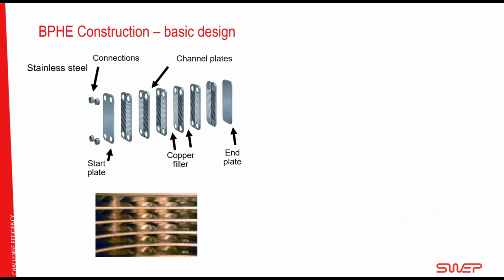Two words about the brazed plate technology. There are other webinars that go more in depth about this. This webinar is about fouling, so I will be very brief here. The brazed plate heat exchanger is made of channel plates, which create the heat transfer area. We have a start plate and an end plate to put everything together and make it strong enough to keep the pressure. All the main components are made of stainless steel: the end plate, the channel plates, the connections, everything. In between the plates, there is a metallic filler, which normally is copper. During the manufacturing process, where we put these heat exchangers in a furnace, the filler material becomes like a metallic glue, keeping the stainless steel plates together. So once they are baked, they are hermetically sealed, with very good strength and heat exchanger efficiency.